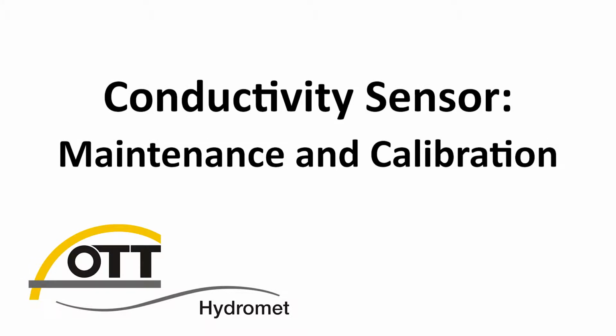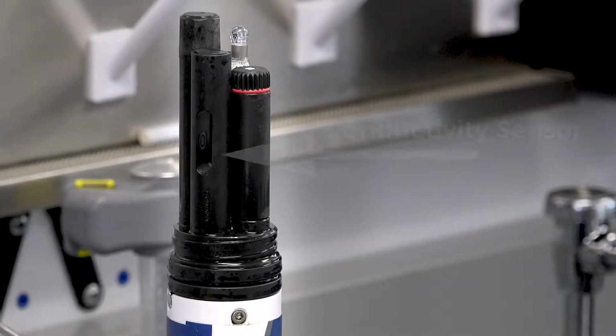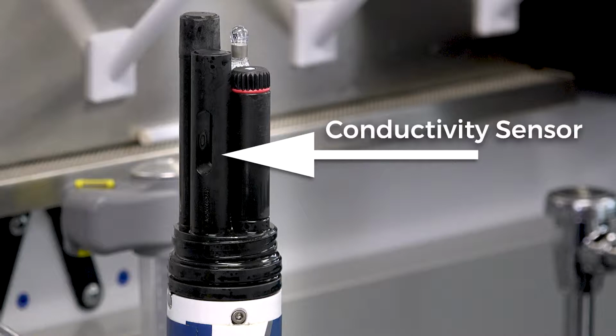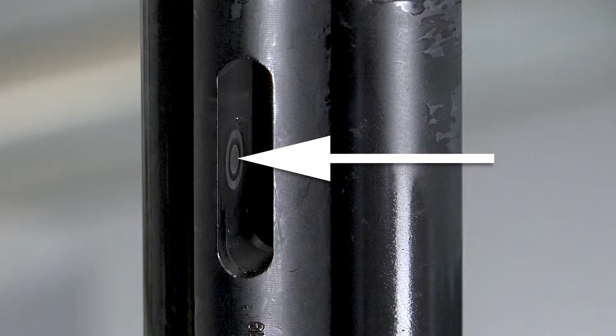Maintenance and calibration of the conductivity sensor. The conductivity sensor measures the ability of water to conduct electricity across a set distance between graphite conductors of a known size. When the conductivity is known, the salinity and total dissolved solids can be calculated and displayed.